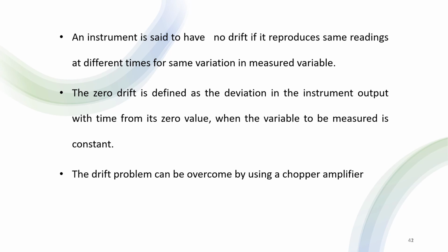So, an instrument is said to have zero drift if it reproduces the same readings at different times for the same variation in the measured variable. The zero drift is defined as the deviation in the instrument output with time from its zero value when the variable to be measured is constant. The whole instrument calibration may gradually shift by the same amount.